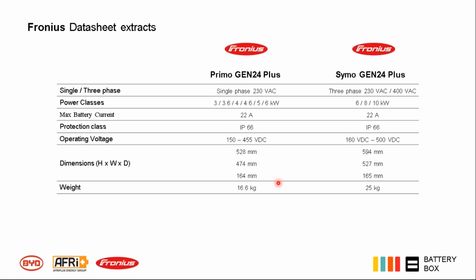Here we can see the two Fronius Gen 24 Plus inverters. The Primo Gen 24 Plus is single phase, and you get everything from 3 kilowatts to 6 kilowatts. It's IP66, which lends a lot of flexibility into where you can install it, especially if your battery is also IP55.